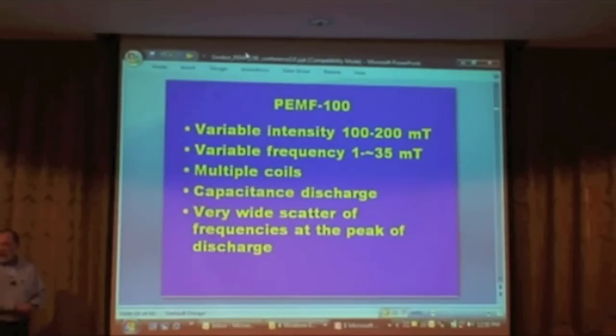So that's a very powerful field, relatively speaking, without costing $1 million. And so you don't always have to get to the size of an MRI machine to have that kind of thing accomplished. So variable frequency between about 1 to 35 hertz. So when you put it at the highest intensity, it has the lowest frequency, and that's about 1 cycle per second. When you turn it all the way down in terms of intensity, almost to where you're not going to feel anything at that point, you're really actually still getting about 100 millitesla, 1,000 Gauss. Okay, that's a lot of power still, without causing muscle contraction. And you've got multiple coils.